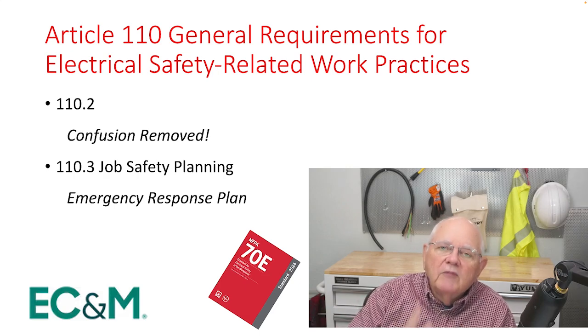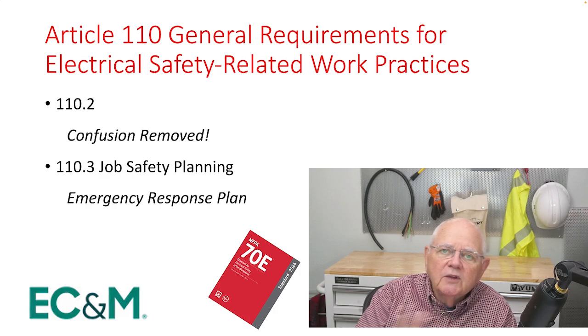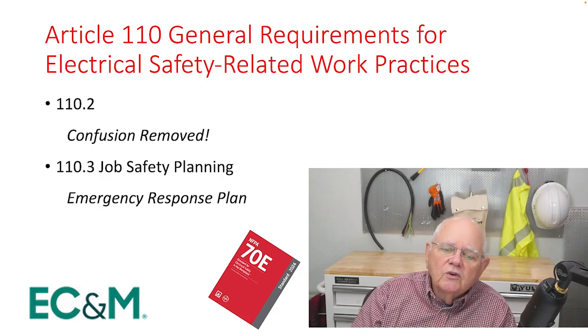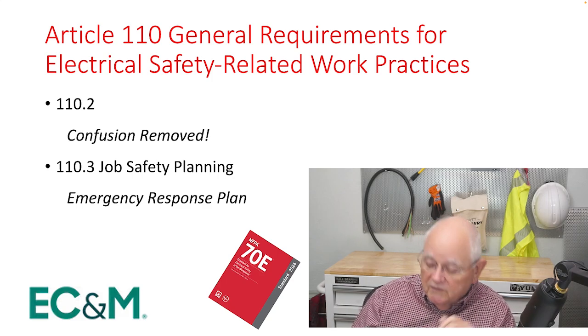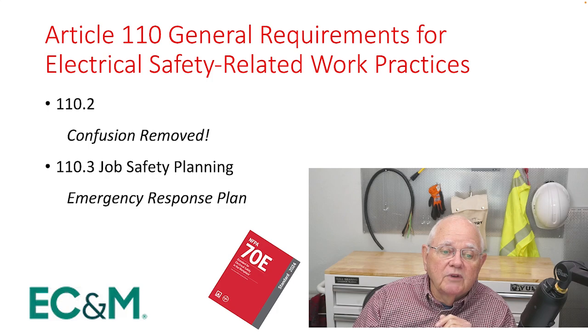No, maybe you need a second person, you see. So think about it. Maybe you need another person with a radio, or inside of that equipment, being able to stand there and throw that disconnect or breaker or whatever it is and shut the power off. So your emergency response plan and your job safety plan definitely tie together. Now we have the requirement in 110.3 to address that emergency response plan as part of job safety planning.